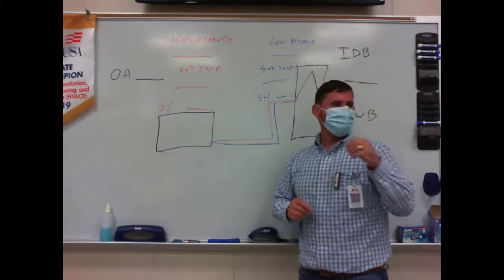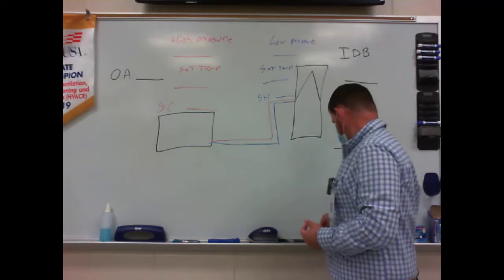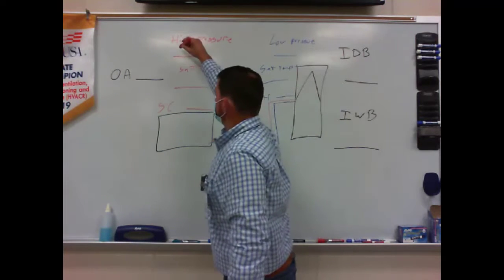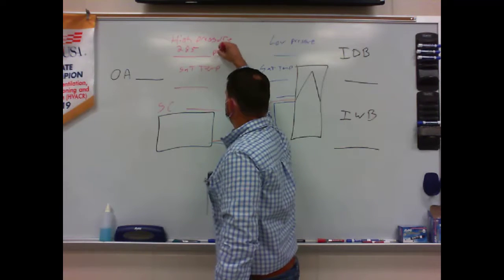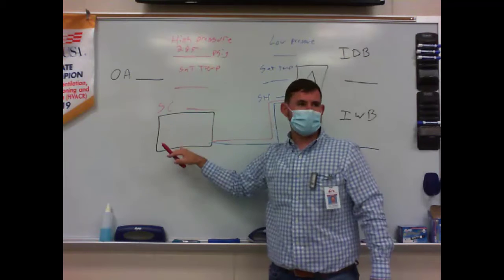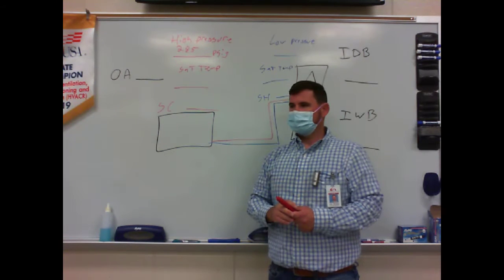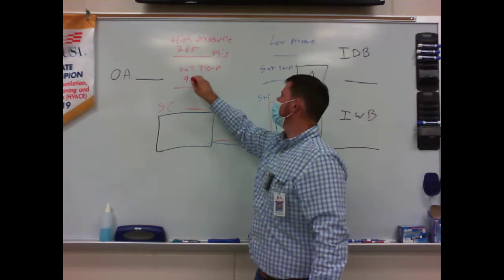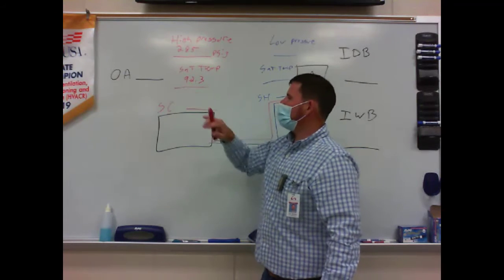Edward, what did you and Brian have on your high side pressure? 285 PSI. So 285 PSI. What was my saturation temperature in my condenser at that pressure? 92.3. All right. So I was saturating at 92.3.